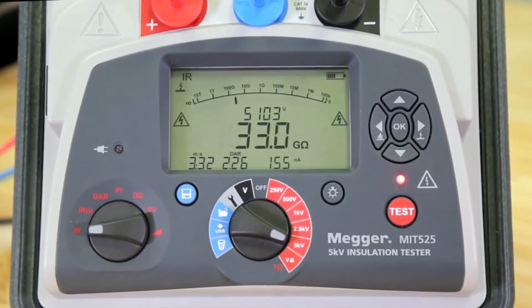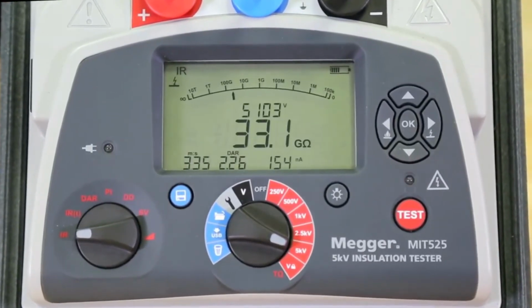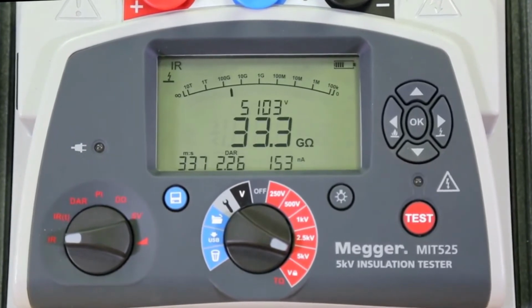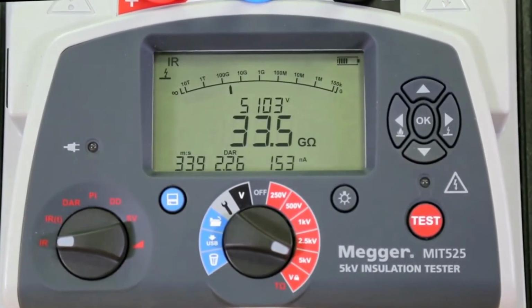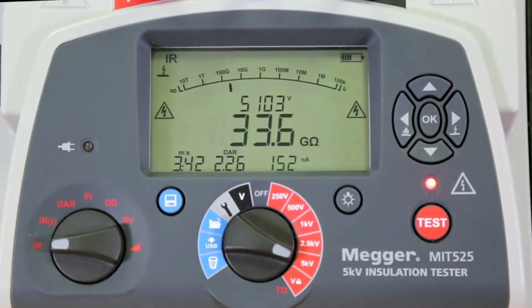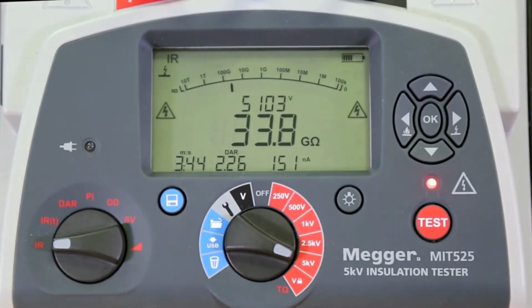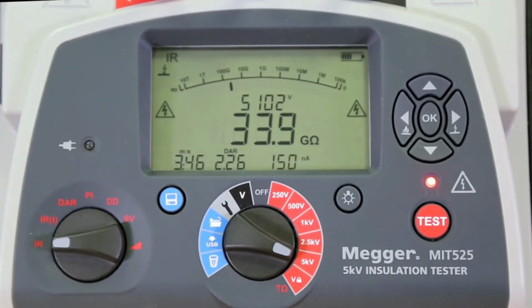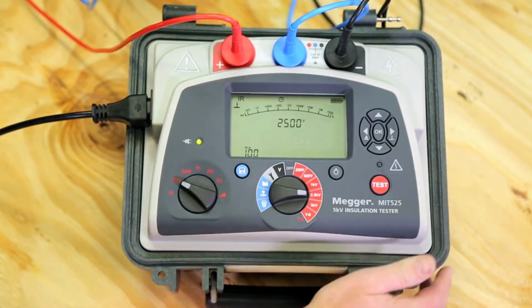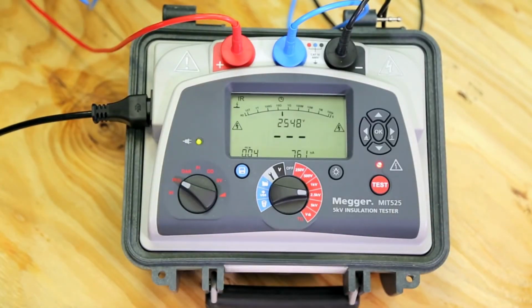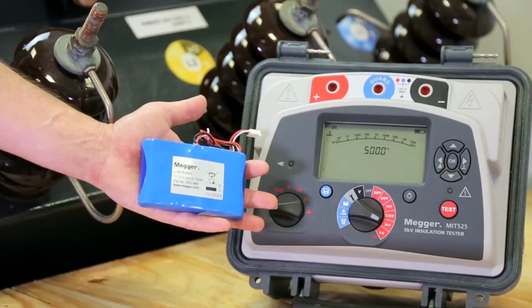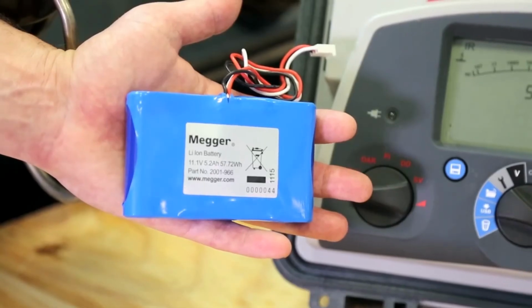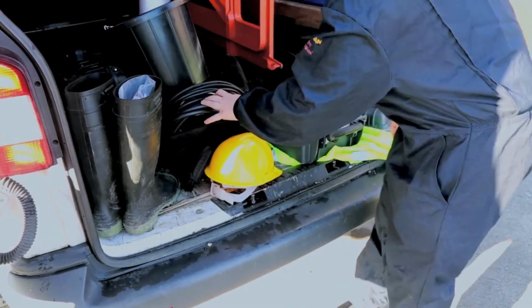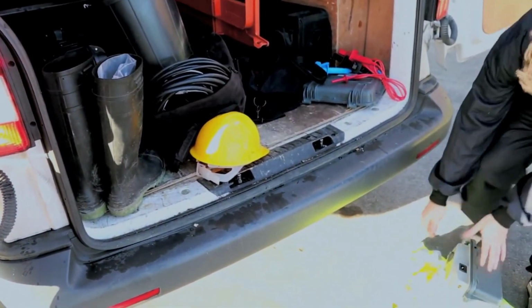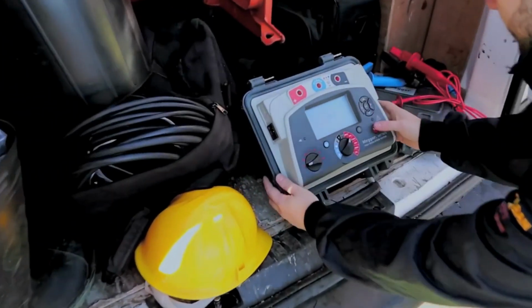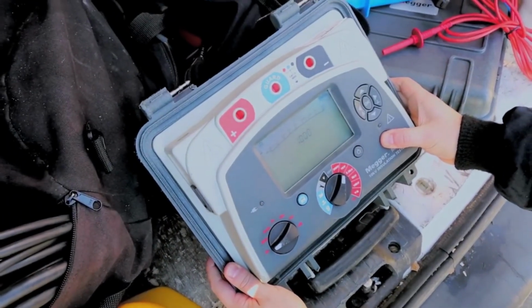The MIT range gives 5% accuracy to at least 1 teraohm, the sort of value expected in substations. Stable readings are essential. They can be affected by electrical noise. The Megger insulation testers have high noise immunity for use in power environments. Always ready to go, they're battery powered but can operate on mains too. The MIT uses light lithium batteries that are fully charged in 2.5 hours. Like all Megger instruments, the MITs are designed to be tough.